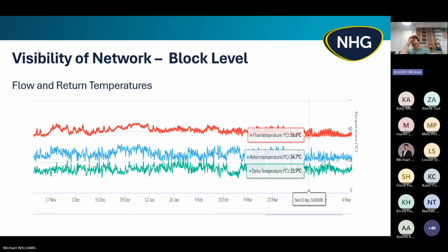And this is an image, again, taken from Guru Pinpoint. We have Guru meters connected to our risers at block level, and we can see that the flow temperatures and the return temperatures are looking very good. The flow temperatures through the risers are 56 degrees Celsius, and we have quite a strong delta T, a 21 degree delta T. That means the temperatures are coming back through the system much lower, and it shows us that the HIUs are doing their job well in terms of giving the heat to the resident for their heating and hot water services. So we're really happy with those performance indicators on the flow and return temperatures, and it indicates that the system is still working very well, 2-3 years post the works being carried out. Next slide, please.